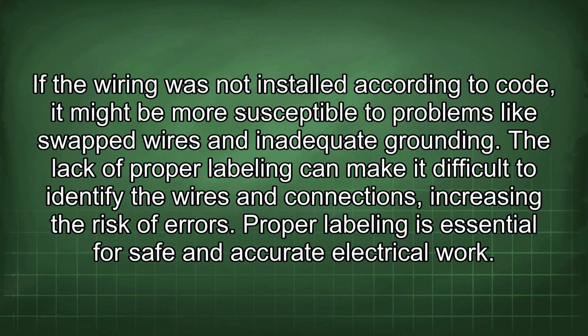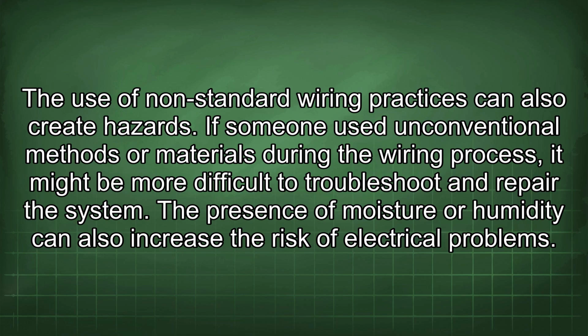If the wiring was not installed according to code, it might be more susceptible to problems like swapped wires and inadequate grounding. The lack of proper labeling can make it difficult to identify the wires and connections, increasing the risk of errors. Proper labeling is essential for safe and accurate electrical work. The use of non-standard wiring practices can also create hazards. If someone used unconventional methods or materials during the wiring process, it might be more difficult to troubleshoot and repair the system. The presence of moisture or humidity can also increase the risk of electrical problems.